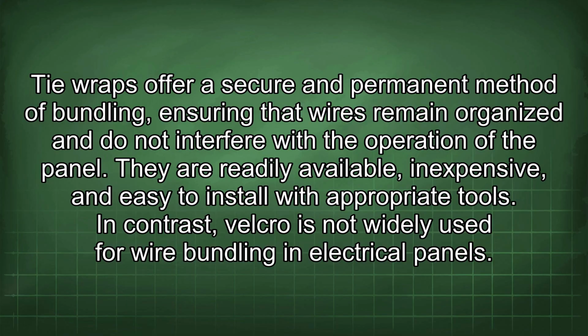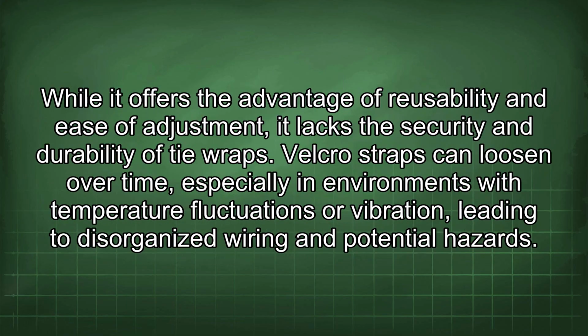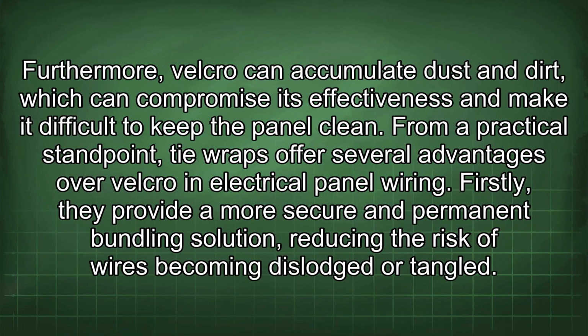In contrast, Velcro is not widely used for wire bundling in electrical panels. While it offers the advantage of reusability and ease of adjustment, it lacks the security and durability of tie wraps. Velcro straps can loosen over time, especially in environments with temperature fluctuations or vibration, leading to disorganized wiring and potential hazards. Furthermore, Velcro can accumulate dust and dirt, which can compromise its effectiveness and make it difficult to keep the panel clean. From a practical standpoint, tie wraps offer several advantages over Velcro in electrical panel wiring.